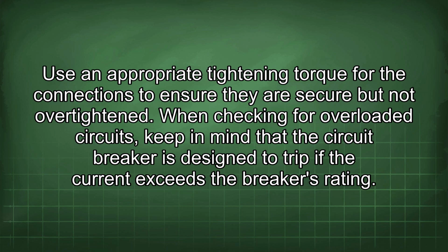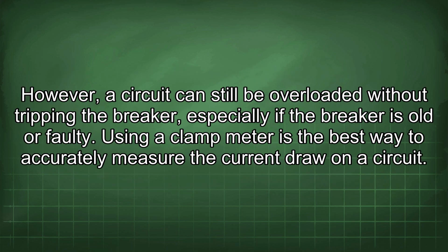When checking for overloaded circuits, keep in mind that the circuit breaker is designed to trip if the current exceeds the breaker's rating. However, a circuit can still be overloaded without tripping the breaker, especially if the breaker is old or faulty. Using a clamp meter is the best way to accurately measure the current draw on a circuit.